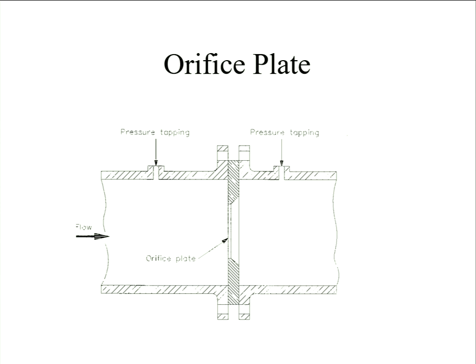I think the metallurgy, I've never really thought about the metallurgy itself. It's just the same. I think they're just usually stainless steel. But the size of the orifice will dictate the flow range. So a small orifice will generate a lot of dP for a flow. A bigger orifice is less. So you've got to size it appropriately. Otherwise, you start to generate too much dP, and you do get pressure losses across your orifice plate.